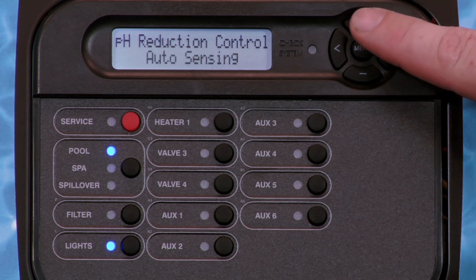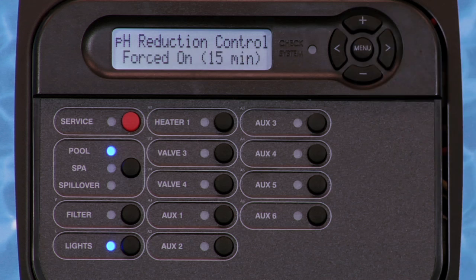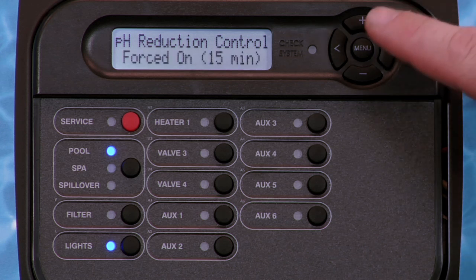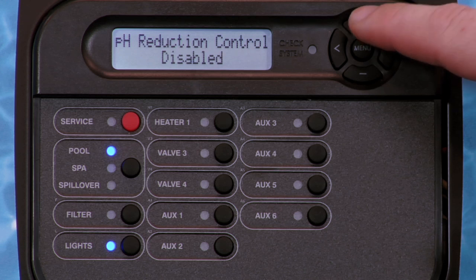Pressing the plus key will change the bottom line of the display to pH reduction control forced on 15 minutes. This setting is used for troubleshooting purposes to force on the reduction control output to verify proper operation of the acid feed pump or solenoid valve for a CO2 tank. Auto-sensing is the preferred setting when using Sense and Dispense.